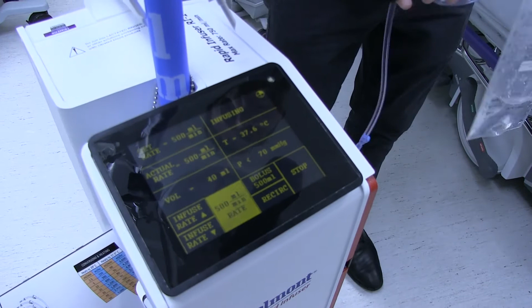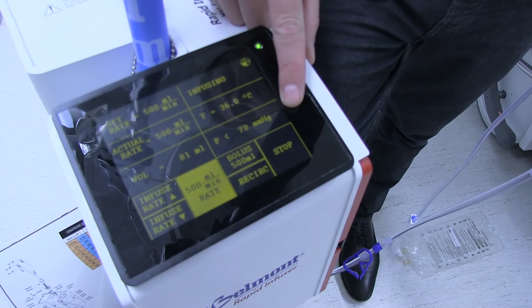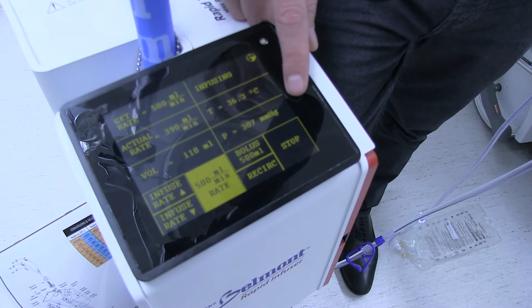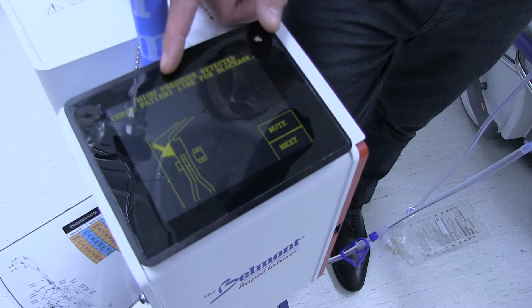Now if you start to go too fast through a small line, you can watch the pressure rise here. This is the patient line pressure. As that goes up, the machine starts to slow itself down to try to compensate. It's trying to keep this pressure below 300. And if it can't, and if the pressure rises too high, it clamps itself shut: high pressure detected, check patient line for blockage.